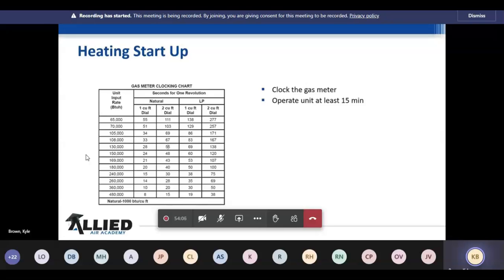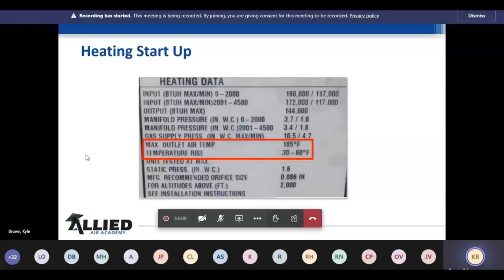But one of the things I see that's overlooked the most is the temperature rise. When we check the temperature rise on these units, you've got to make sure that your economizers and your fresh air dampers, whether they be manual or motorized, are all closed. And if you know you're going to run fresh air, or you have a minimal amount of fresh air you have to put in there, you have to take that into account for your 30 to 60 degree rise. So when you have that damper shut and you're right there at a 30-degree rise, you've got to think in the back of your mind, well, I've got to have 5 or 10% fresh air.